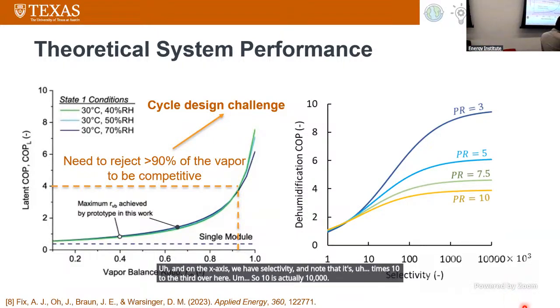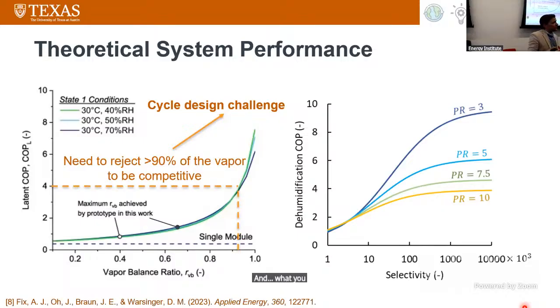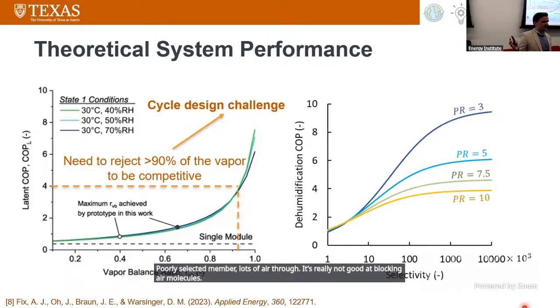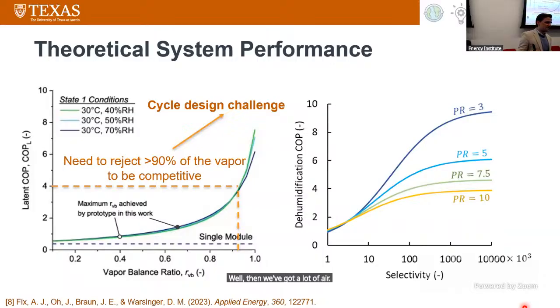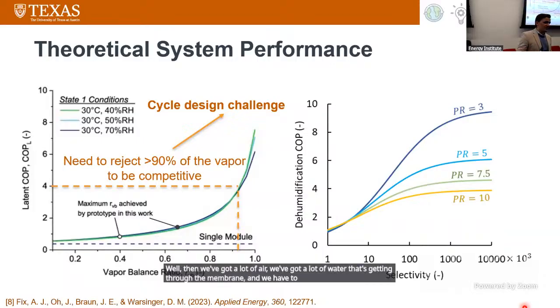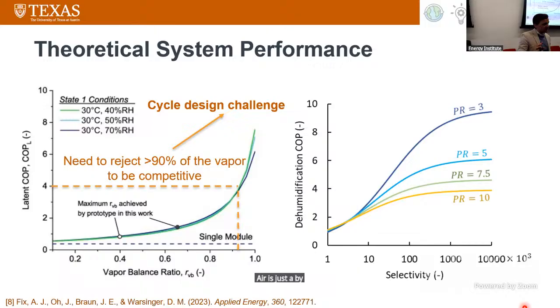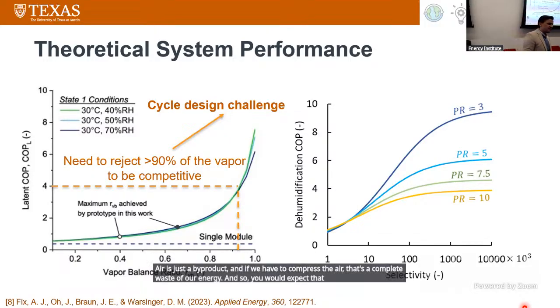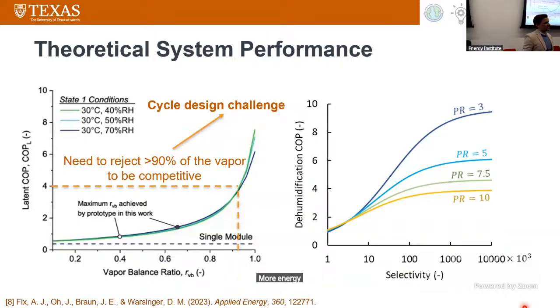What you would imagine is if you have a really poorly selective membrane, it lets lots of air through. It's really not good at blocking air molecules. Well, then we've got a lot of air, a lot of water getting through the membrane, and we have to compress all of that gas. All we really want the system to do is pull the water and compress the water. Air is just a byproduct, and if we have to compress the air, that's a complete waste of our energy. So you would expect that lower selectivity means more air is leaking into the system, which means more gas is being sent to the compressor, which means more energy is being spent on compression processes.